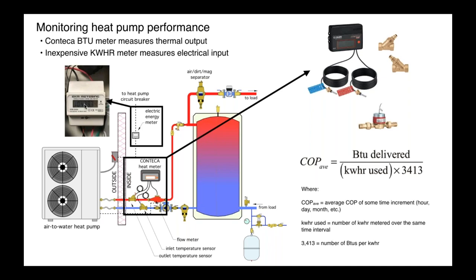And then for about $100, you can get one of these little meters. Basically, you just run your 240-volt supply to the heat pump through it, and that gives you kilowatt hours. So if you want the COP, I'll say the average COP over any period of time, we just take the total BTUs that the Conteca meter gives us, divide it by the kilowatt hours that this meter gives us, and we convert kilowatt hours over to BTUs by multiplying with that factor. So it's pretty easy to put a heat meter in and monitor the performance of that heat pump.